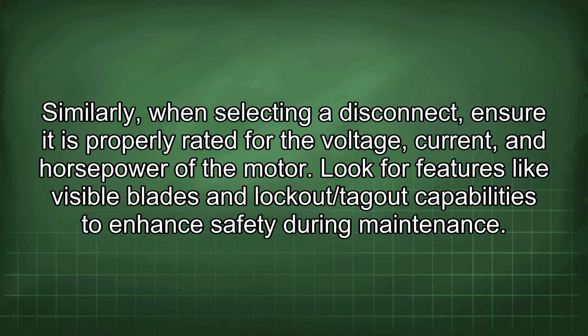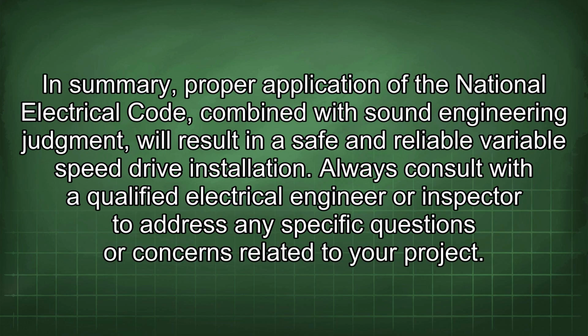Similarly, when selecting a disconnect, ensure it is properly rated for the voltage, current, and horsepower of the motor. Look for features like visible blades and lockout/tagout capabilities to enhance safety during maintenance. In summary, proper application of the National Electrical Code, combined with sound engineering judgment, will result in a safe and reliable variable speed drive installation. Always consult with a qualified electrical engineer or inspector to address any specific questions or concerns related to your project.